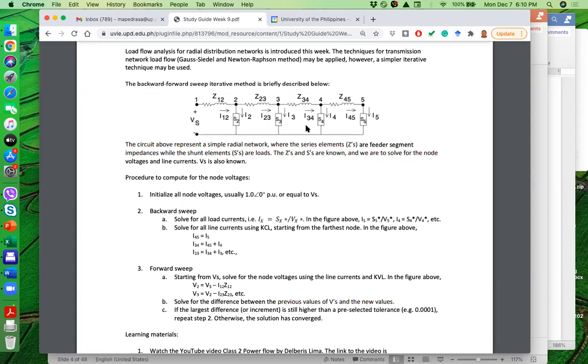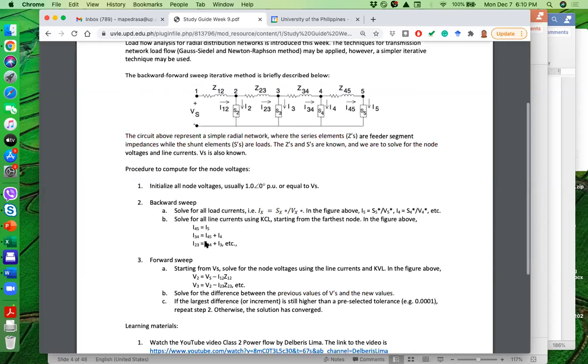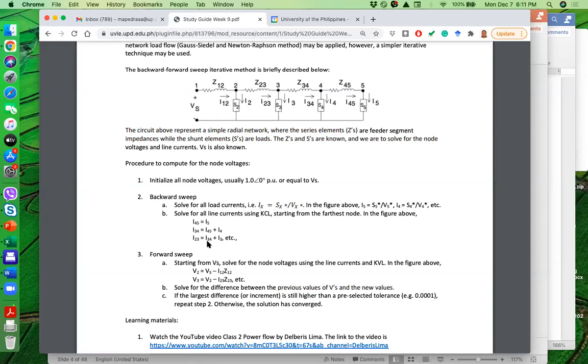Once we have estimates of the currents drawn by the nodes, the next step is to solve for all branch currents using KCL. So I45 equals I5, I34 equals I4 plus I45, I23 equals I3 plus I34, and I12 equals I2 plus I23. That is essentially the backward sweep — solving for all currents in the network. We started at the node farthest from the substation and worked back to Vs.